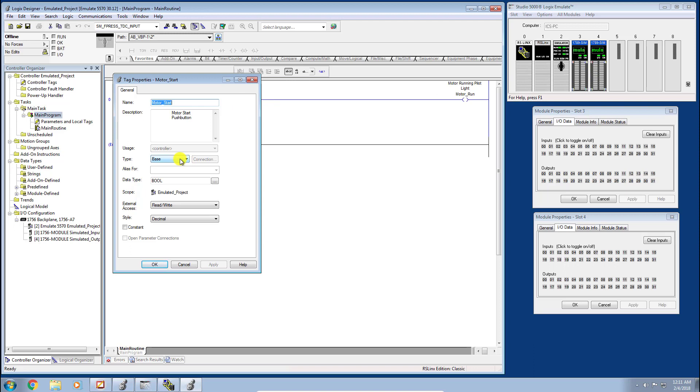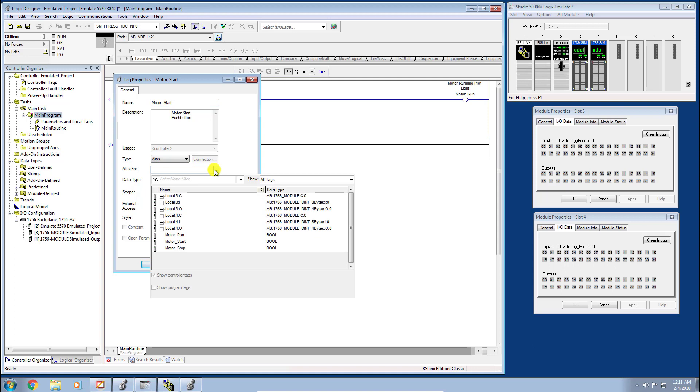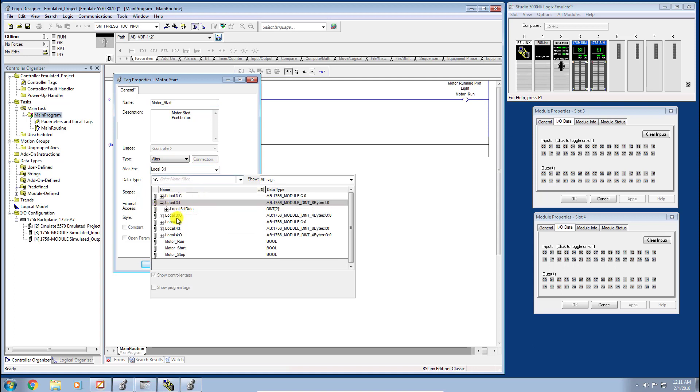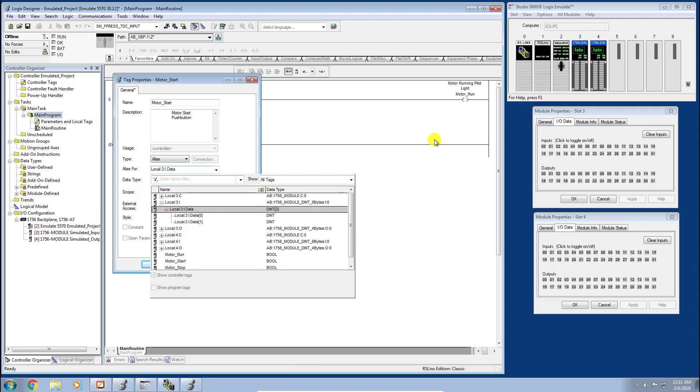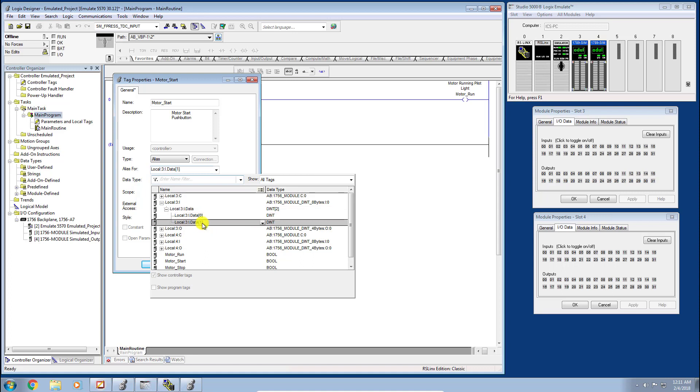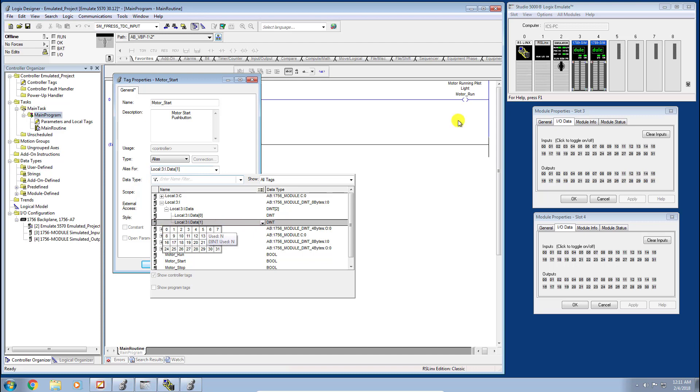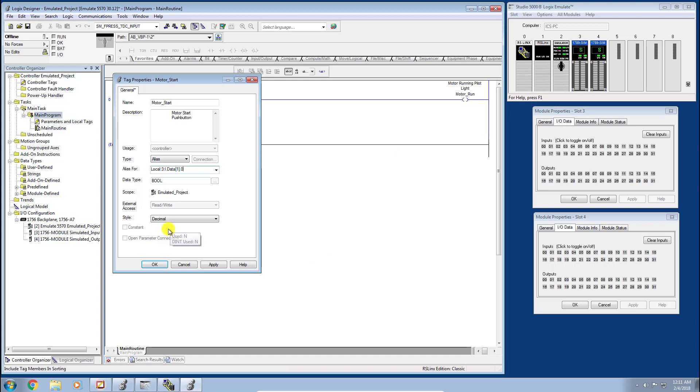We're going to go ahead and change this to alias, and then we're going to drill into the Alias For column and select our data for slot 3. Remember, because we're using these simulated I/O modules, we have to use this array element one word. We want to hit this little flyout here and let's make it the first bit or bit zero on slot 3 module's input. We just click that and that's it, it's that simple. Now motor start is an alias for the first I/O point zero on slot 3 of our simulated input module.